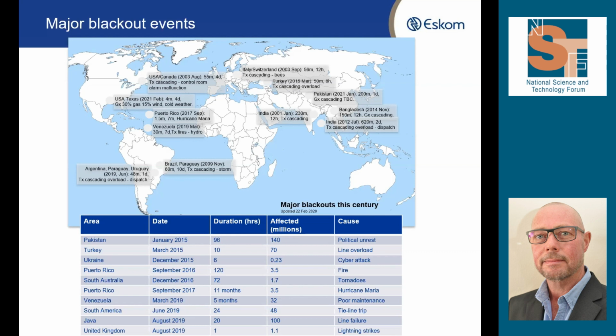It's also during those instances that we had the operation of the under-frequency load shedding, where we did get down to about stage 3. So we removed about 10% of the load on that island, but we have never had beyond stage 1 under-frequency load shedding on the main grid. So in other words, as soon as the frequency got down to 49.2, and we have had a number of those instances over the last 10 years or so, we would automatically remove that load, and it's so fast that it does actually recover the frequency back into normal operating range.